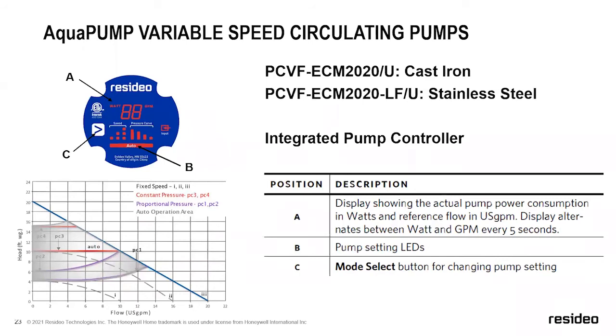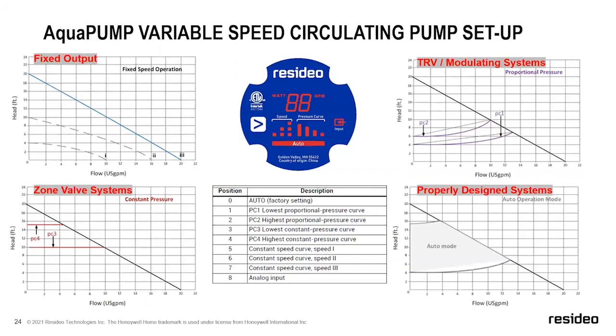Now getting into the different operational modes, again, I did want to reemphasize that we've got a push button there to cycle between the modes, and it will flash a visual indicator on your wattage and flow rate consumption. And I'm going to jump into what all these different curves mean. So if you look in the bottom left, that is our pump curve with every single different operation mode on one setting. So I'm going to shed some light as to what these mean and where you're going to use them. So I broke out the individual curves in different settings so that I could talk about each one. And I'm going to jump around this slide, to be honest. So the first thing I want to do is highlight the auto mode. This is where I would set every single system that you operate within.